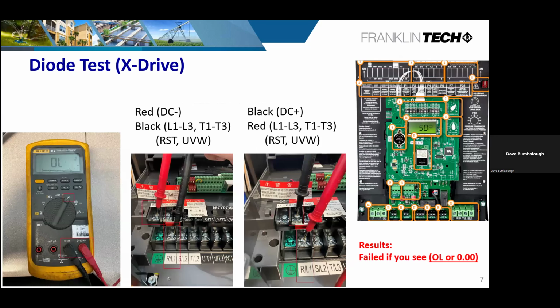But the test that I referred to, the diode test, works very well on drives. And as you can see here, I'm showing you a couple of pictorials of some drives that are out there. The way you conduct this test is you're actually setting your meter on diode. And what you've got to remember is this is basically a DC test, so it is polarity sensitive.